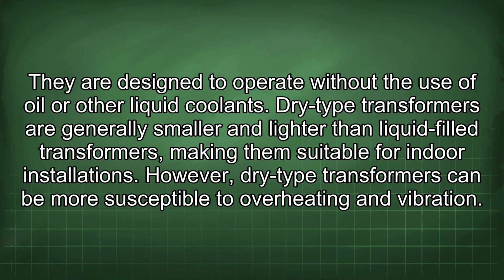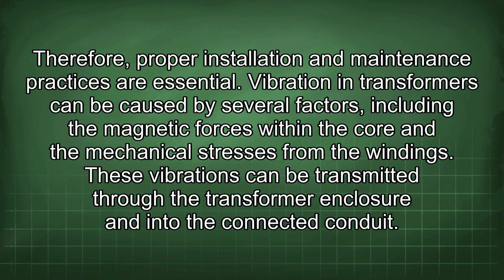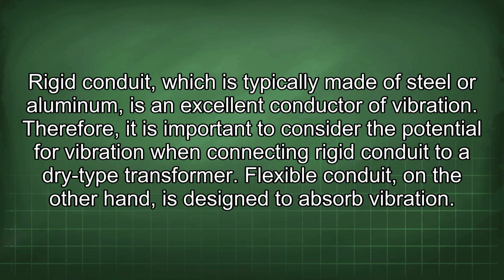However, dry-type transformers can be more susceptible to overheating and vibration. Therefore, proper installation and maintenance practices are essential. Vibration in transformers can be caused by several factors, including the magnetic forces within the core and the mechanical stresses from the windings. These vibrations can be transmitted through the transformer enclosure and into the connected conduit. Rigid conduit, which is typically made of steel or aluminum, is an excellent conductor of vibration. Therefore, it is important to consider the potential for vibration when connecting rigid conduit to a dry-type transformer.